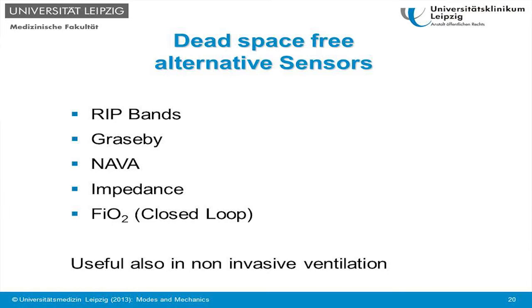There are also alternatives for the flow sensors which are dead space free. RIP bands, Graseby, NAVA, which will be covered this afternoon by my colleague Peter Riemensberger, impedance measurement and even FiO2 measurement closed loop, which I cannot cover today because of time constraints. And all these methods are also useful in non-invasive ventilation, where you have a lot of leaks, which make it very difficult to use flow sensors and interpret the flow sensor readings by a machine trying to trigger a patient.